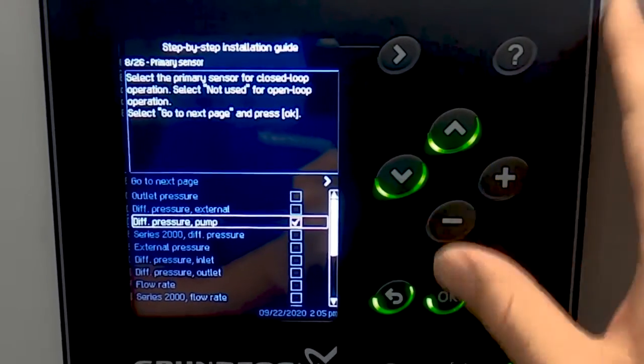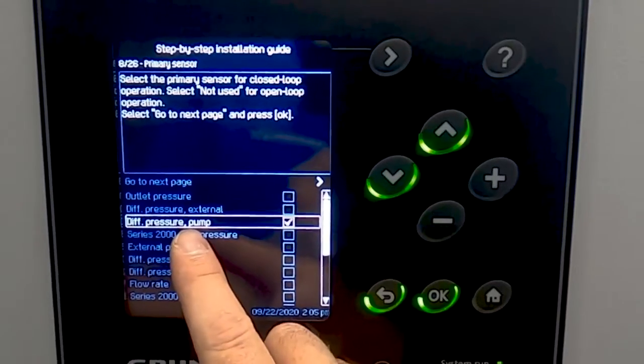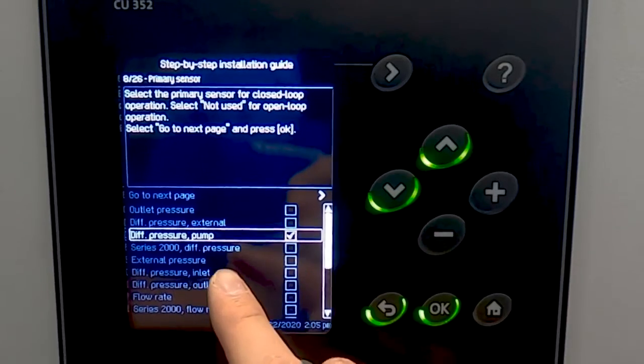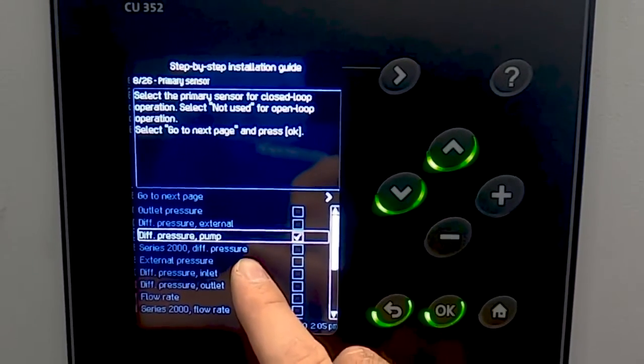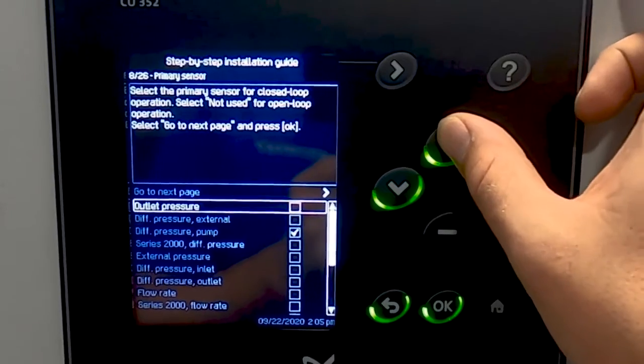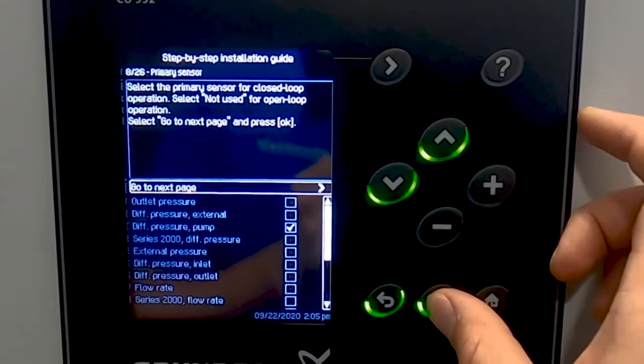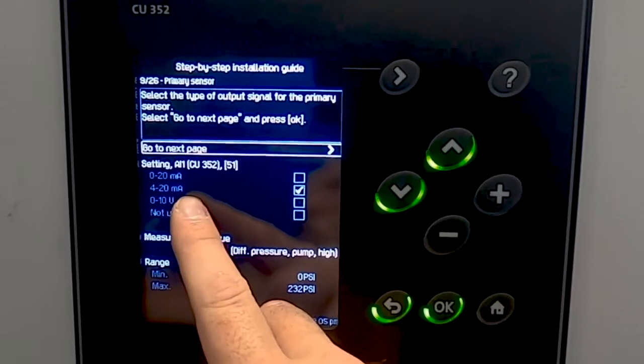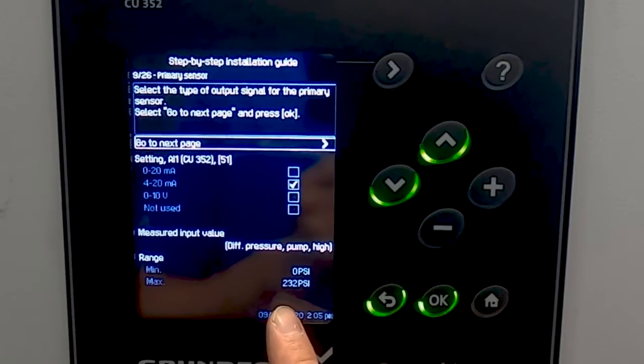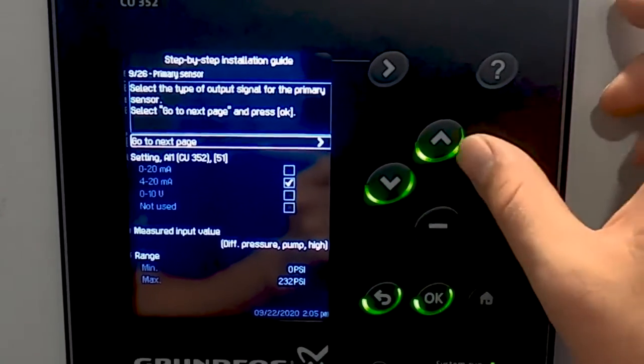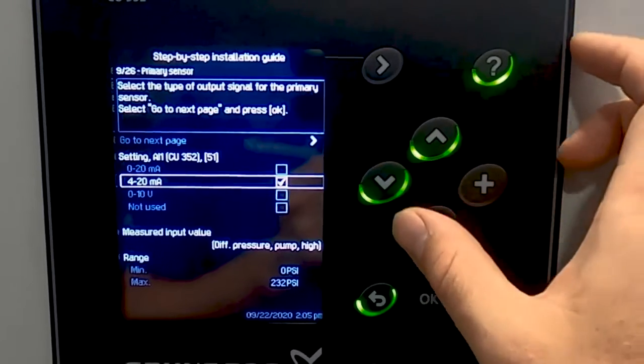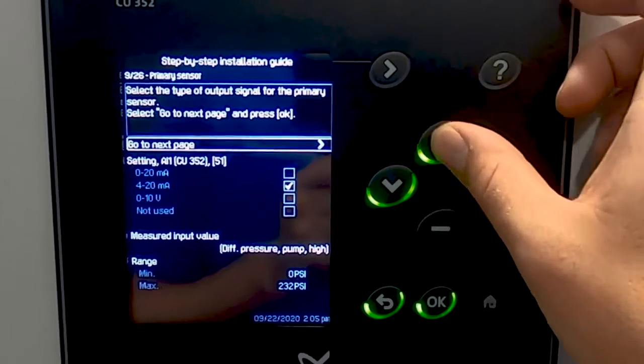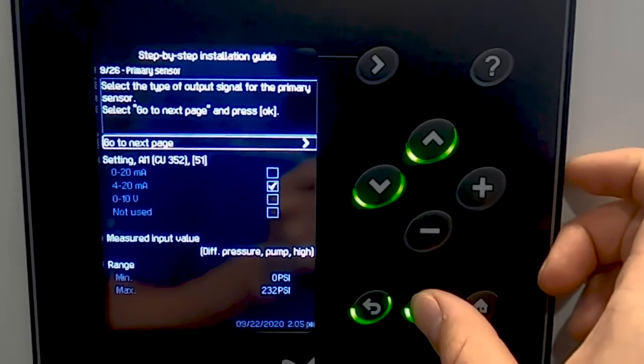Since our system will be for HVAC, we're going to pick differential pressure pump. This will allow us to use the two transducers on the suction and discharge for a differential pressure. Once you have this selected, go to next page. From here, you select the type of transducers — you just need to verify the information by looking at the transducer and verifying it on screen: 4 to 20 milliamps as well as the range of the transducer. Once these have been verified, you can proceed to the next page.